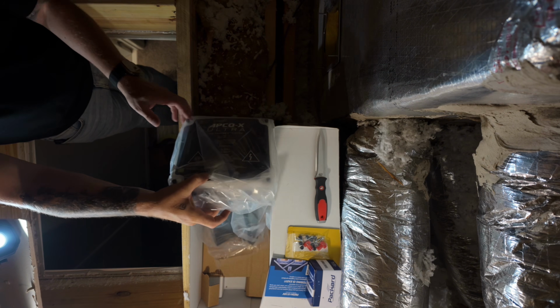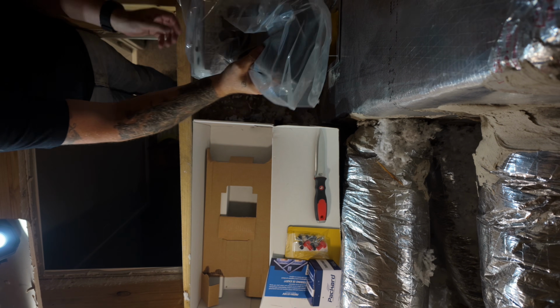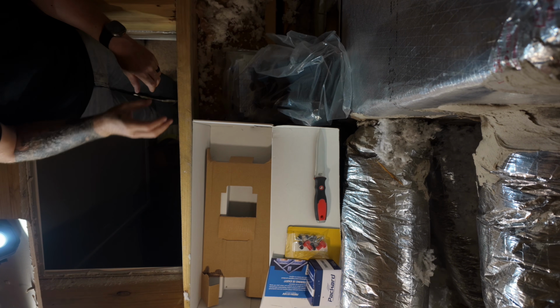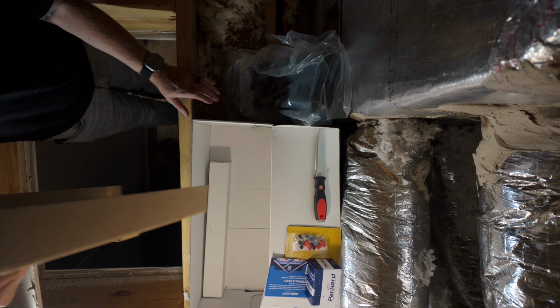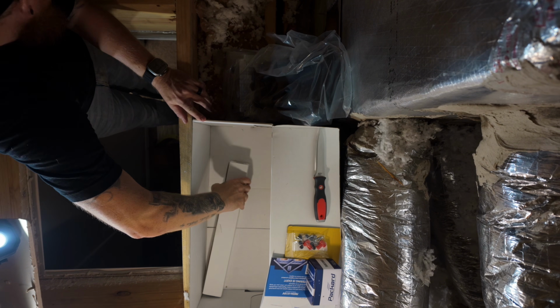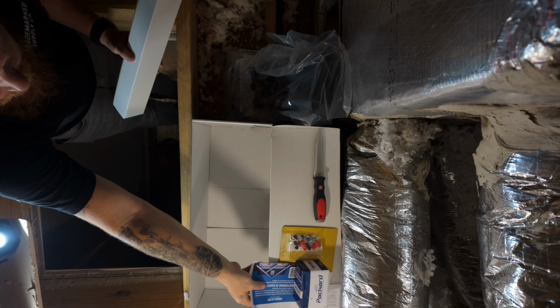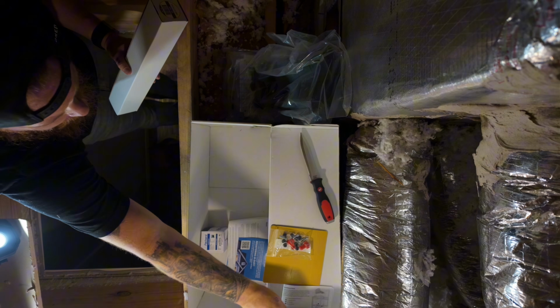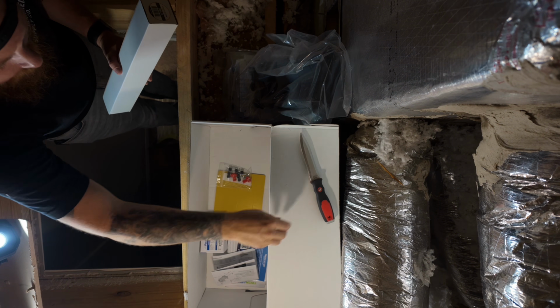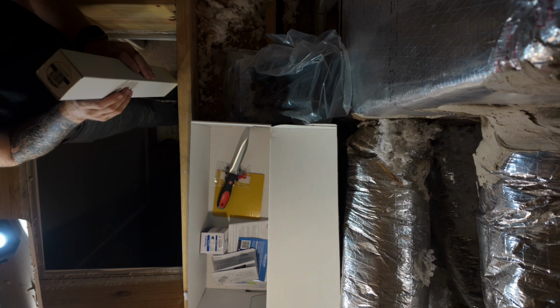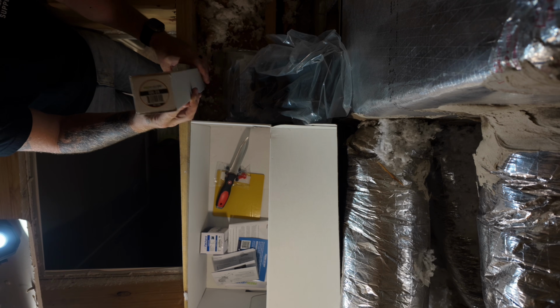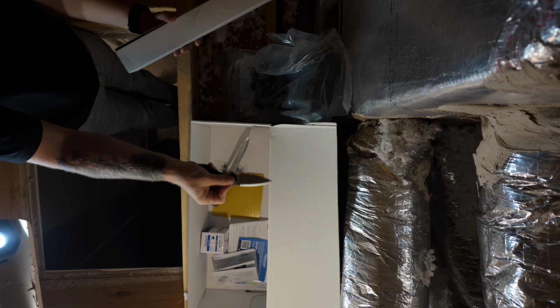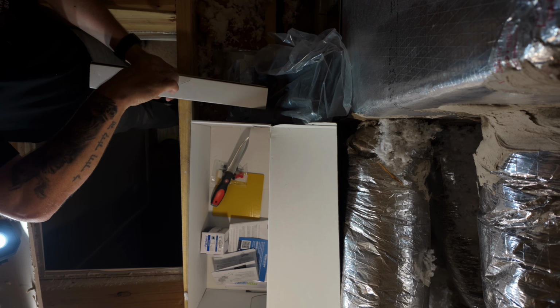Inside the box, you'll find the whole housing for the APCO-X that has the carbon filter on the end. It's also supplied with a dedicated transformer. Always use the transformer — some people say you'll be fine, but in personal experience I've had it rob power from the contactor outside, and that was on a new install. Ever since then, I'll always put the transformer in so I don't have any of those issues.